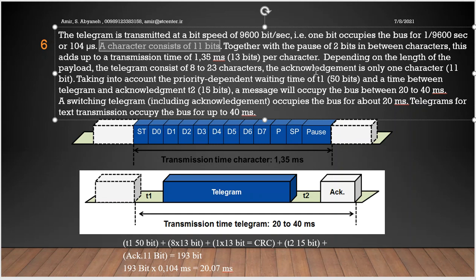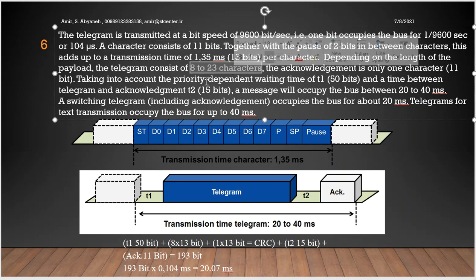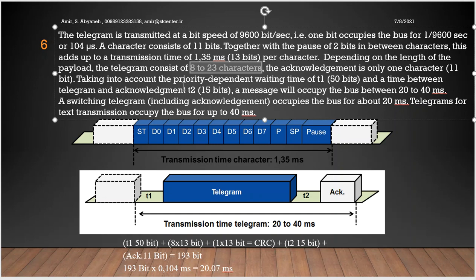Depending on the length of the payload, which means useful data, the telegram consists of 8 to 23 characters. So it is important to know that if your useful data is bigger, it takes more time to transmit. The acknowledgement is only one character, 11 bits. Taking into account the priority-dependent waiting time of T1, 50 bits, and the time between the telegram and acknowledgement T2, 15 bits, a message will occupy the bus between 20 to 40 milliseconds. So you can prove it this time.